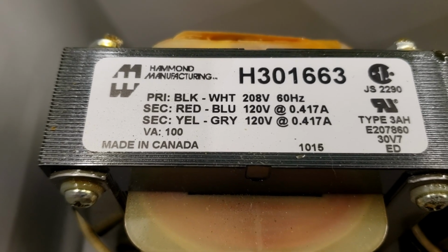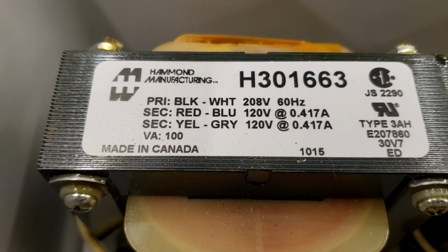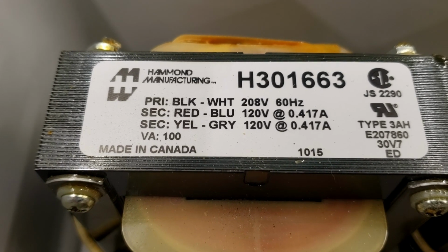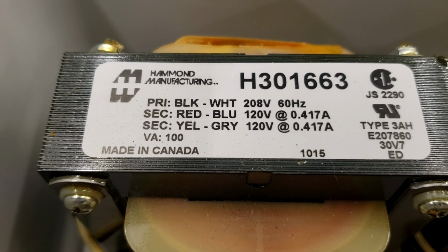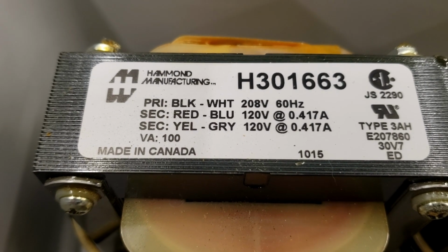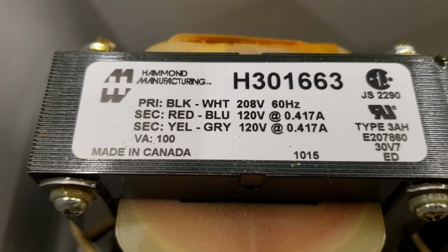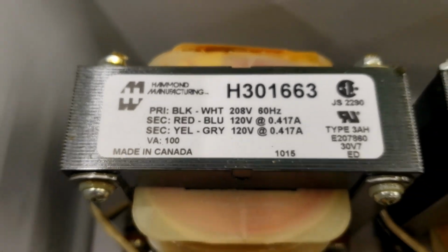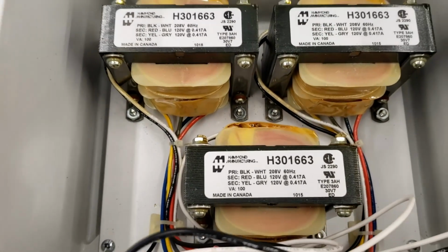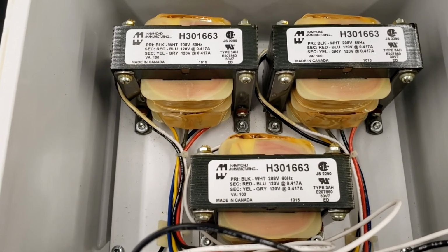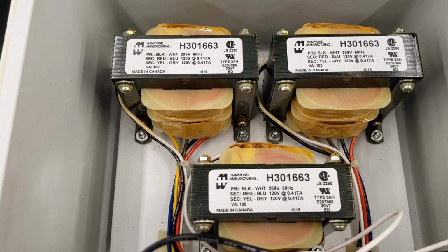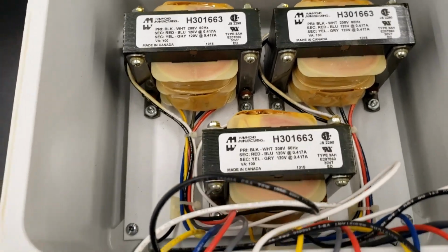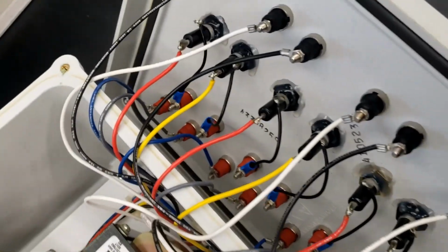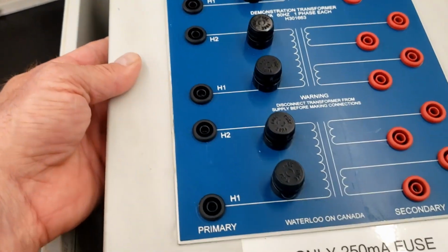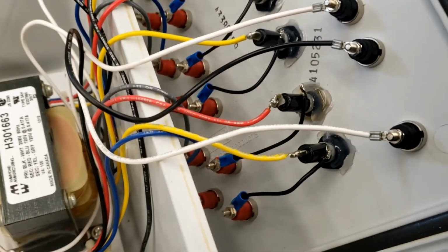Looks like we got 0.4 amps that they're rated for on the secondary. Obviously 60 hertz because we're in Canada. Another thing to notice is the VA, they're 100 VA transformers. We're not connecting up a load to these guys. We're just looking at the voltage that comes out when we connect them up in single phase or 3-phase configurations. So we don't have to worry about having too much VA for lighting loads or anything like that. Those connections come out and then they come to the front of the unit. So these terminals right here that you see for your primary and for your secondary, they're just soldered in on the back of the unit there.